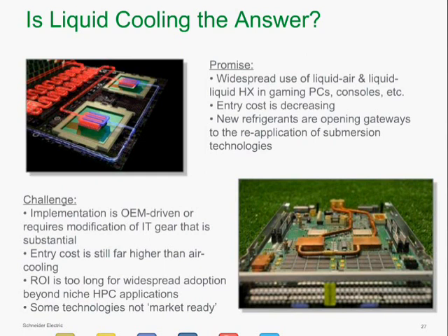Some of the challenges is that it has to be implemented really at the OEM level. The PC or console supplier essentially has to install that prior to shipment. If you're doing that in your data center, it's a pretty difficult, pretty disruptive way to improve the efficiency of your cooling units, and it really requires taking your servers apart, which not a lot of people want to do. So I think one of the biggest issues today for liquid cooling is that it's really kind of a niche application due to the fact that it's disruptive to your IT equipment, and a lot of these technologies really aren't market ready just yet.